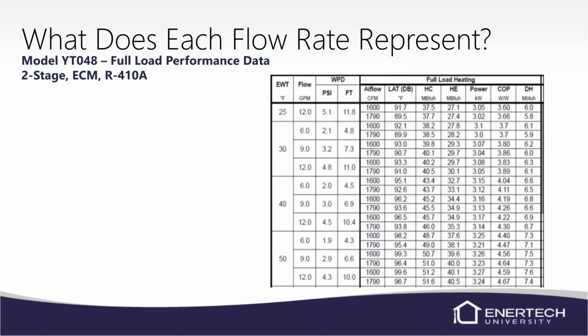If you ever looked at our manuals, you'll notice that we have 3 flow rates listed. So don't just choose one and say, that's what I'm moving. They have a meaning behind them. Now, if you're in full load and you're running 2.1 pound pressure drop at 30 degrees, yes, that's going to tell you you're moving 6 GPM. But that 6 GPM, now we're looking at, this is a YT unit, so it's a packaged 4-ton unit.